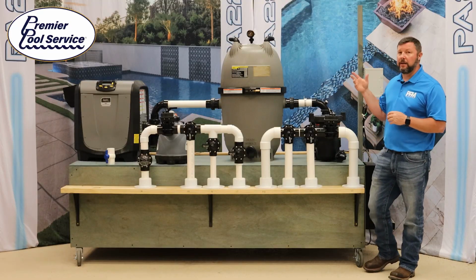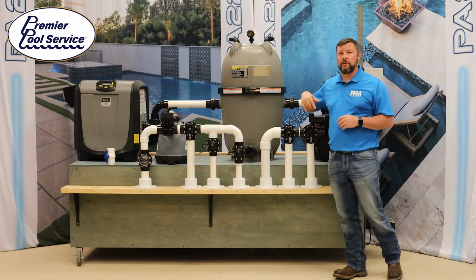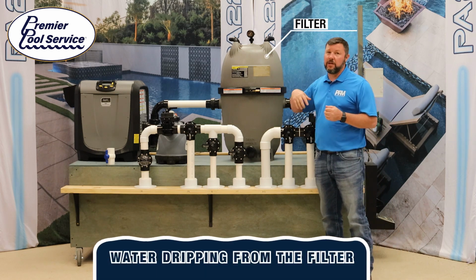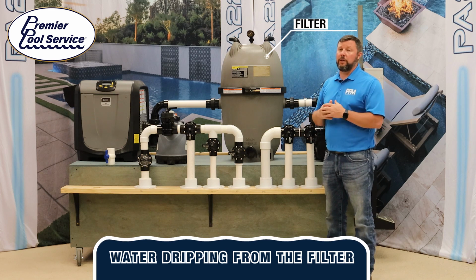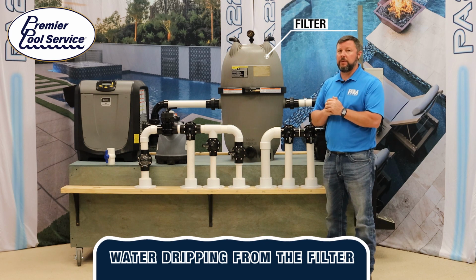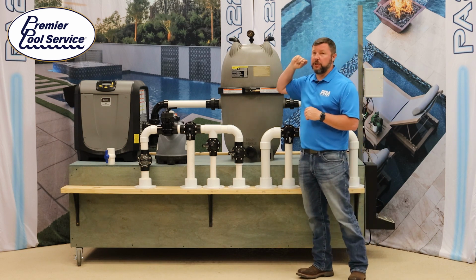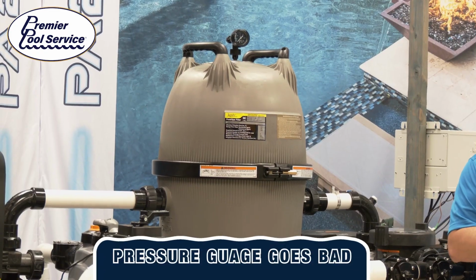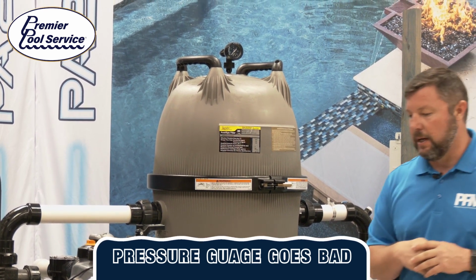Moving on past that, you may see that you have water dripping from your filter. Very common, and it's usually because either the band's not tight enough or really the belly band O-ring that's in there is worn out, probably needs to be replaced. Again, get with your professional to help you out with that. Past that, you have your pressure gauge. They're out in the sun all day long. It's very common for those gauges to go bad and need to be replaced. So that's another one to look at.